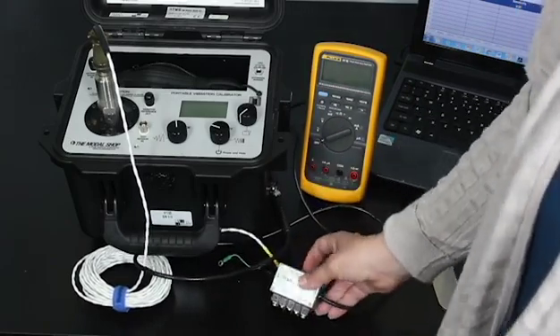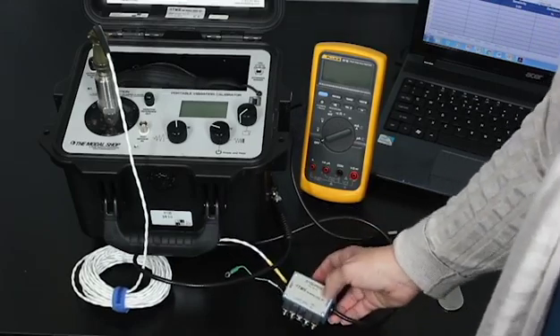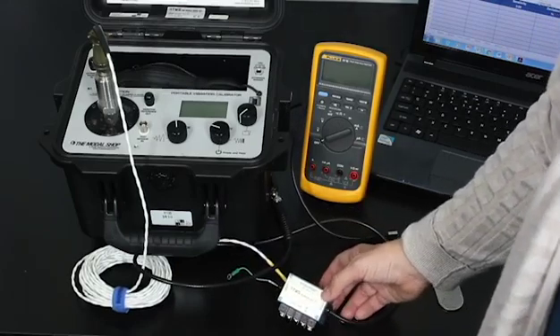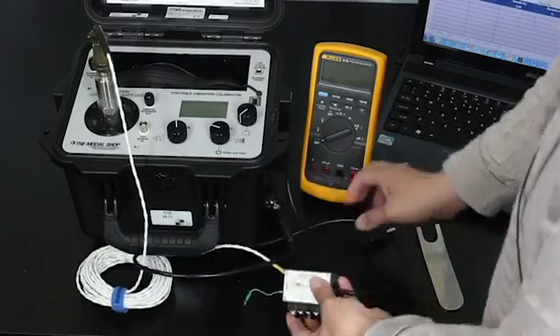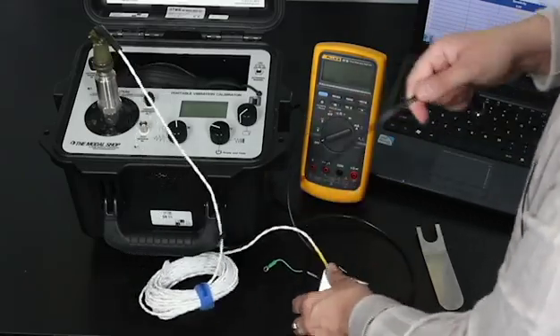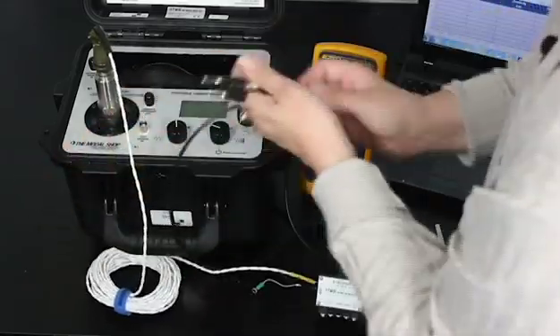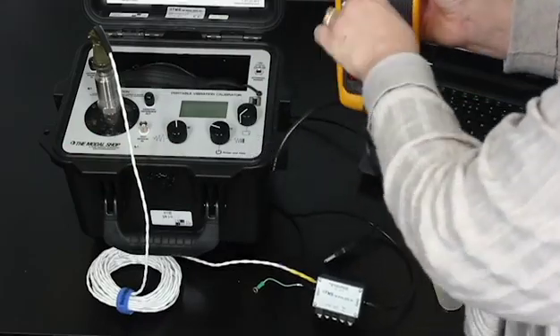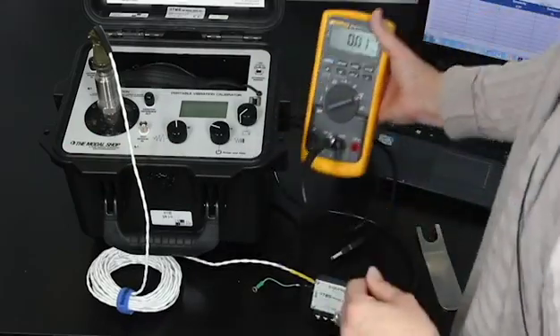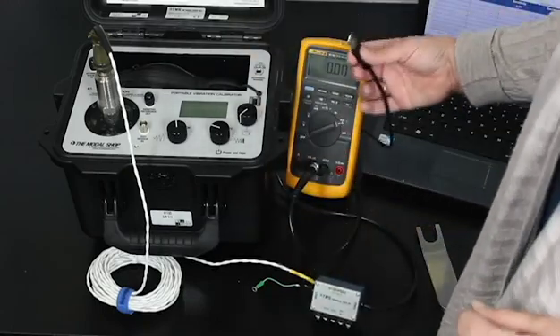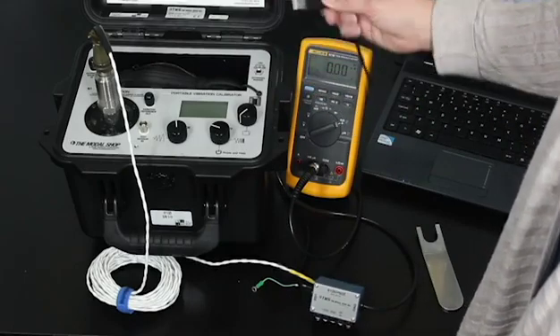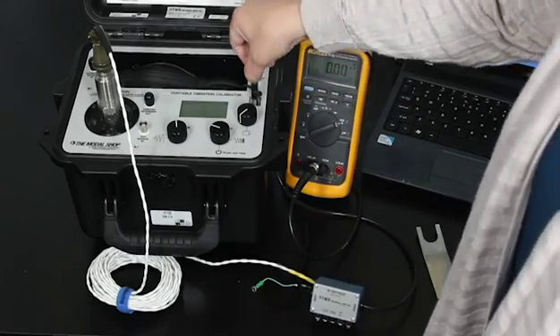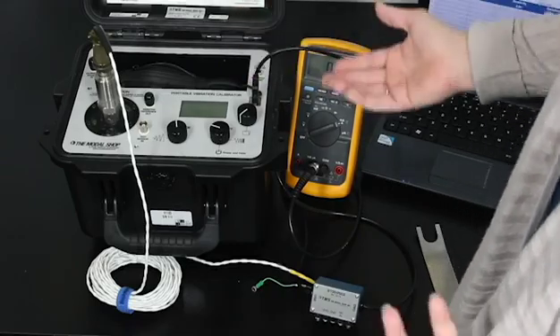And because the PVC itself is only equipped to measure AC voltage signal, we'll need to measure the output of the sensor using a multimeter. So you can see we already have the leads connected here, and we're going to take the output signal from the 9100 PSO2 and connect it to our multimeter. We'll turn that on to measure current. And finally, we will connect the USB to the USB slot on the portable vibration calibrator. And now we're all set up.